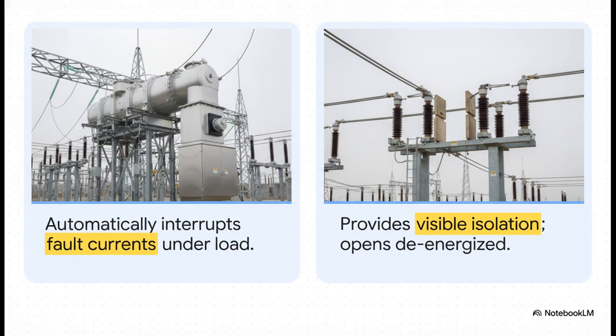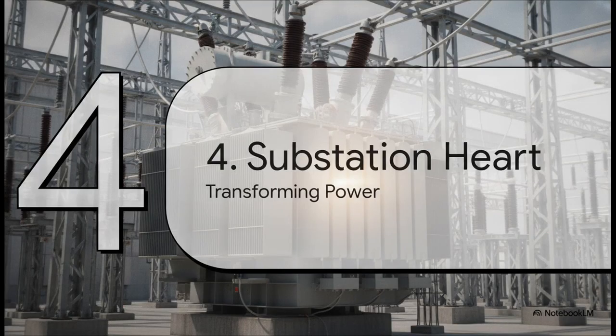The golden rule here is that the isolator is only ever opened after the circuit breaker has completely de-energized the equipment. Okay, moving into section 4, the heart of the substation.